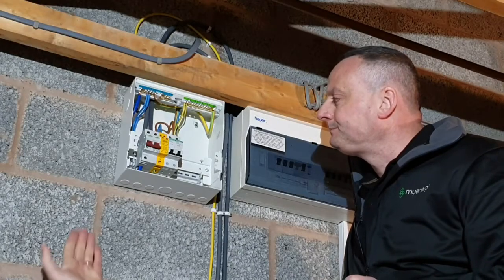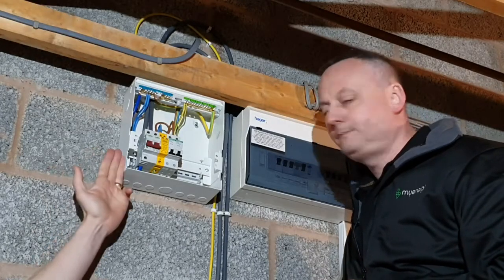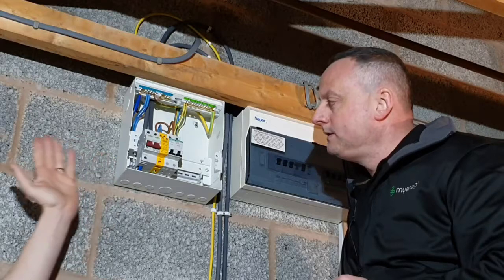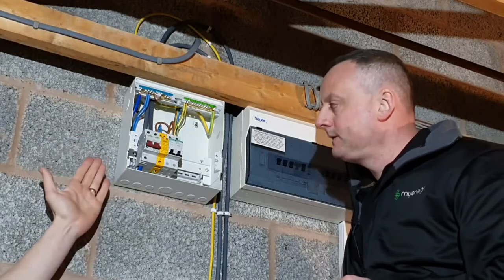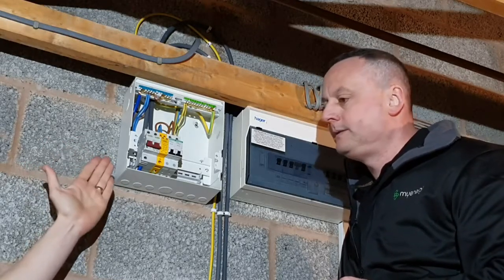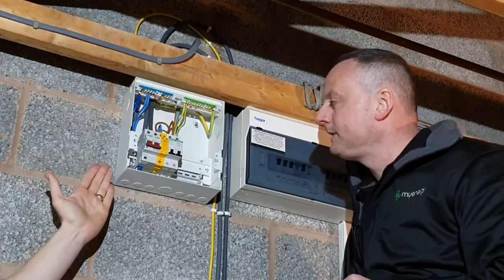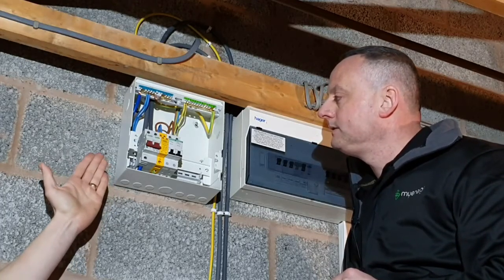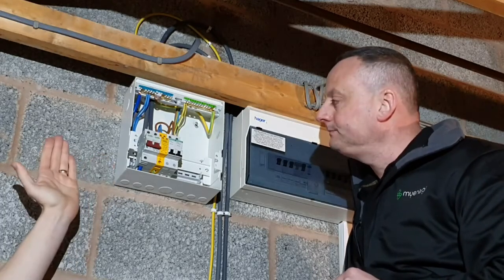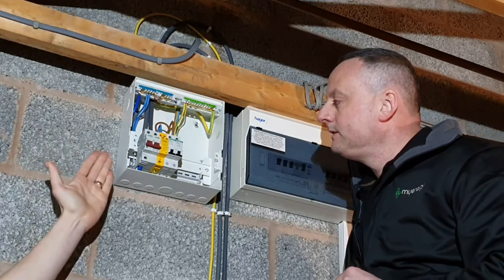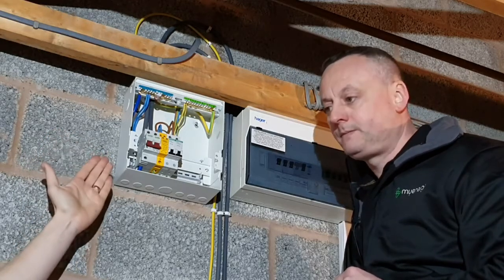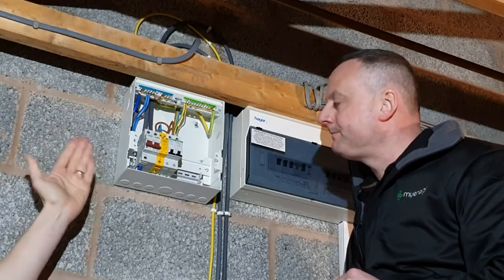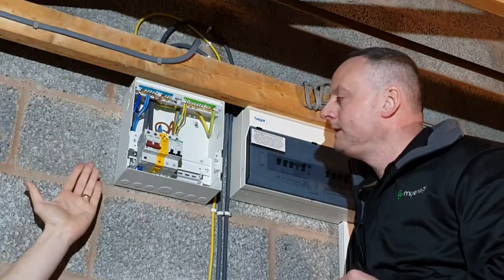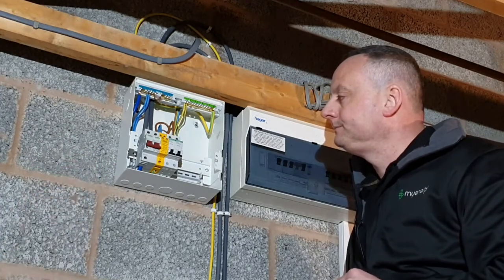The only reason we'd need to start thinking about RCD protection at this point was if we needed to protect the cable that is feeding the EV charging point. The Zappi has the RCD technology built in to protect the socket outlet and the car that's being charged and anyone who may be using that. But we don't need to protect the cable in this installation because we've installed it in such a way that it doesn't require RCD protection. Okay. Basically, we've surface clipped a bit of twin and CPC.